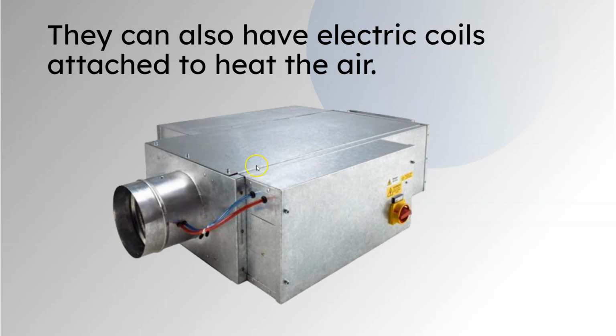On top of water heating, you could actually have electric heating. Since this has a disconnect and high voltage signs in here, this fan power box is going to have electric heat strips. This side goes to the air handler. This side goes to the space, the diffusers. The electric strips are going to be on the far side from the controller. The controller is actually going to sit in this box. The damper probably comes through right about there, and there's a controller sitting in there, and that's what's going to open and close. Now, with electric heat, you obviously have to have some airflow through there, or else the heat strips could catch on fire.